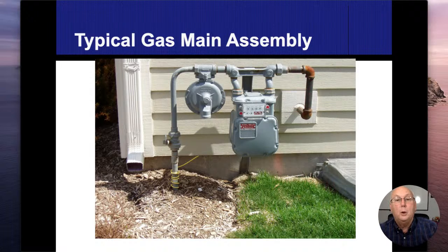So what belongs to the gas company and what belongs to the homeowner, you can see up here is kind of the last part that was painted, this universal fitting. So everything to the right of that that's not painted, that belongs to the homeowner. The gas meter, regulator, and pipes that go down into the earth belong to the gas company. Now, this pipe that we have above ground will be metal, all right? But this metal pipe goes into the earth maybe a foot, maybe 2 feet. It doesn't go far. Most of the gas pipes that we have underground are all going to be plastic.